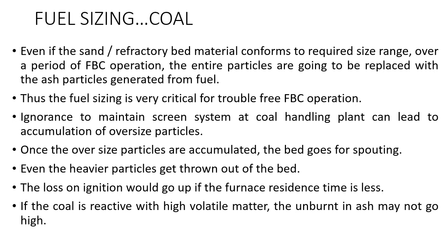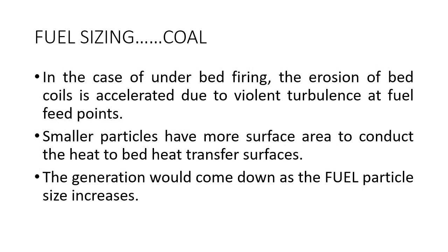In the case of underbed firing, the erosion of bed coils is accelerated due to violent turbulence at fuel feed points. Smaller particles have more surface area to conduct the heat to bed heat transfer surfaces. The generation would come down as the fuel particle size increases.